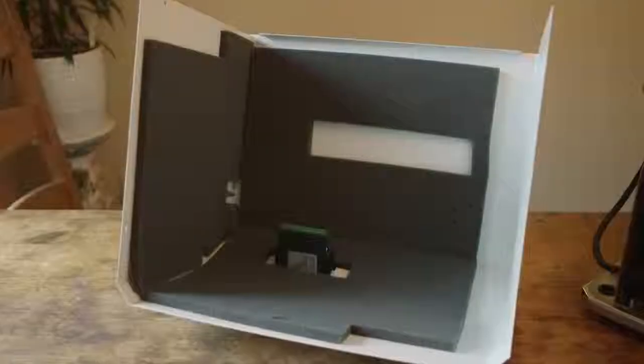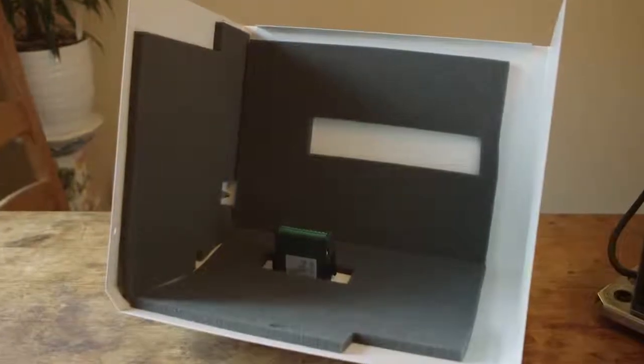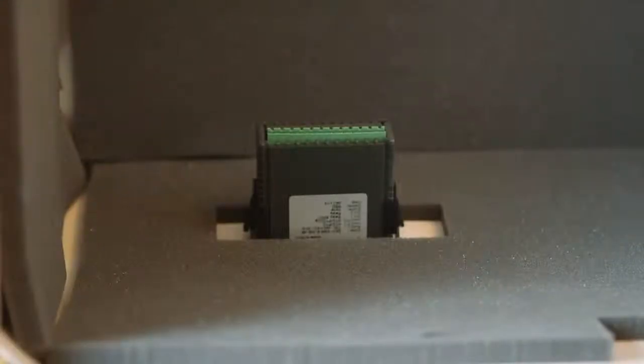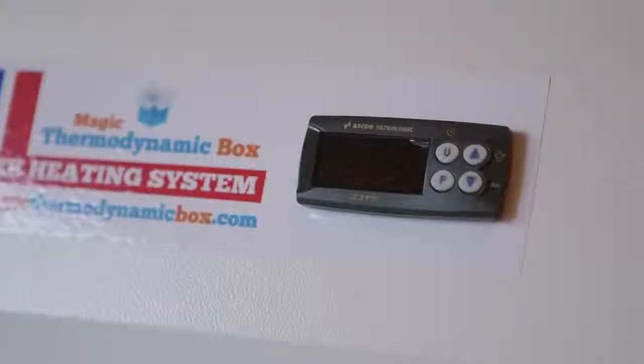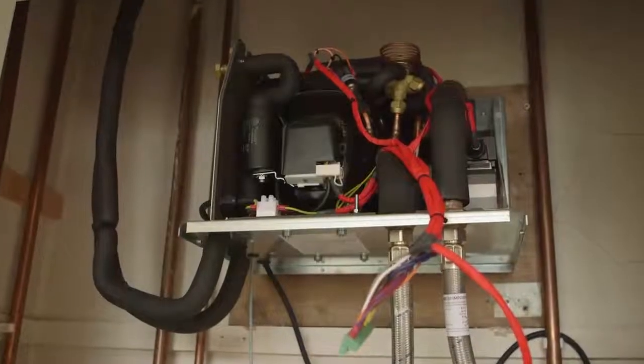The box has excellent insulation and is extremely quiet. On the front of the box is a digital display. This shows the temperature of the water within the cylinder. The thermostat can be configured anywhere between 20 and 55 degrees centigrade. What happens is that the water is heated until it reaches the thermostat control, let us say 55 degrees. The system then cuts out and doesn't start up again until the temperature reduces to 50.